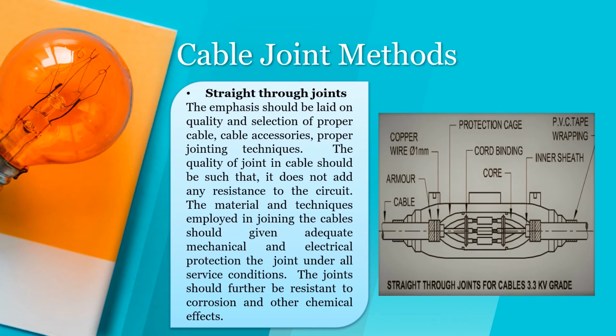The emphasis should be laid on quality and selection of proper cable accessories and proper jointing techniques. The quality of a joint in a cable should be such that it does not add any resistance to the circuit. The material and techniques employed in joining the cables should give adequate mechanical and electrical protection to the joint under all service conditions. The joints should further be resistant to corrosion and other chemical effects.